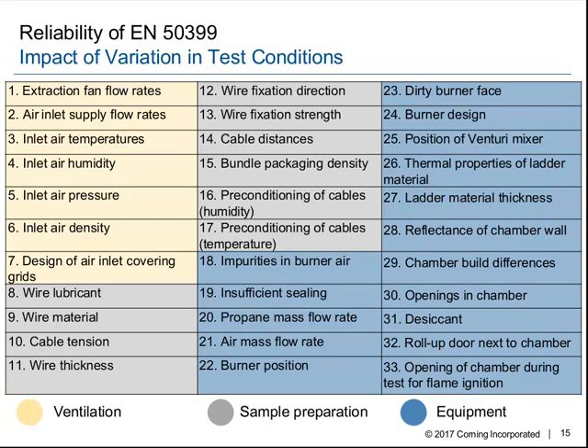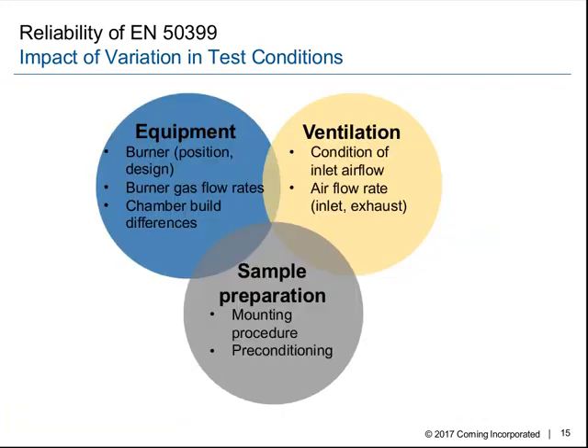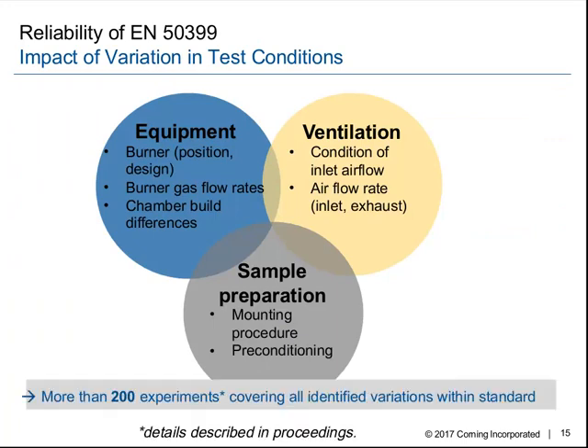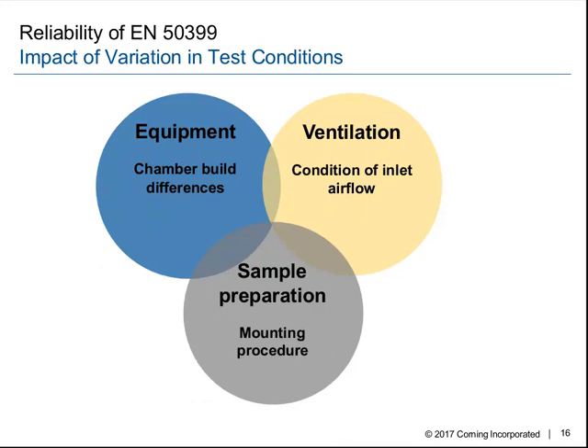In general, one can separate those parameters into parameters dealing with ventilation, with sample preparation, or with the equipment. In sum, we performed more than 200 experiments covering all those identified variations within the standard. Due to brevity, I cannot show you all of those experiments. So today, I would like to focus on the mounting procedure for the sample preparation, the condition of inlet airflow for ventilation, more precisely the humidity, and for the equipment, the results for chamber build differences.